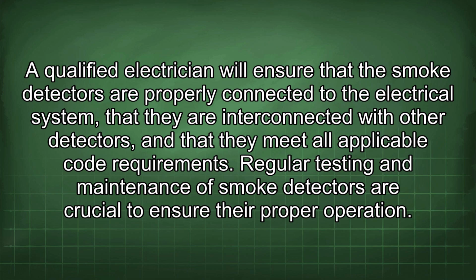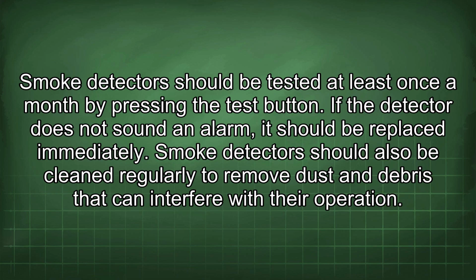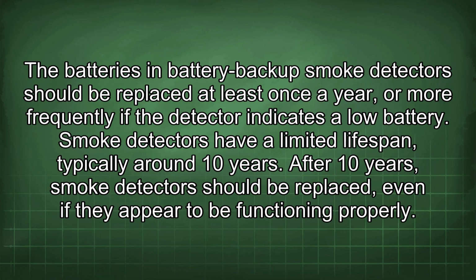Regular testing and maintenance of smoke detectors are crucial to ensure their proper operation. Smoke detectors should be tested at least once a month by pressing the test button. If the detector does not sound an alarm, it should be replaced immediately. Smoke detectors should also be cleaned regularly to remove dust and debris that can interfere with their operation. The batteries in battery backup smoke detectors should be replaced at least once a year, or more frequently if the detector indicates a low battery.